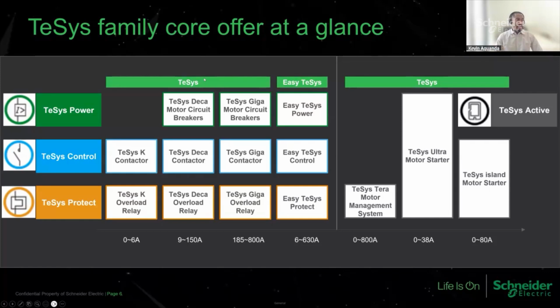And so with this, we have the TeSys offer for more critical applications where there is a need for high performance, very frequent operations. And within TeSys, we have the TeSys K, TeSys Deca, and TeSys Giga offers. And each of these provides motor protection breakers, contactors, overload relays, covering requirements from 0 amps to 800 amperes. So very wide range of applications within this, covering all segments. Then for more standard applications where a cost-effective offer is required, we have Easy TeSys, which is also a complete starter solution with the TeSys Power, Control and Protect options for short circuit, overload, and control of the motors themselves.